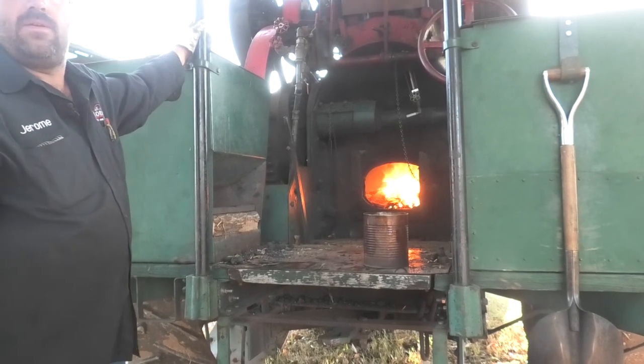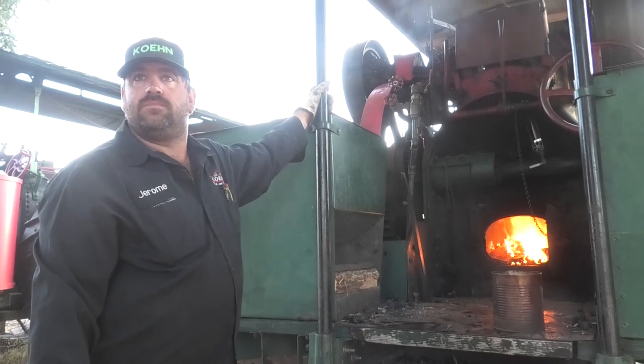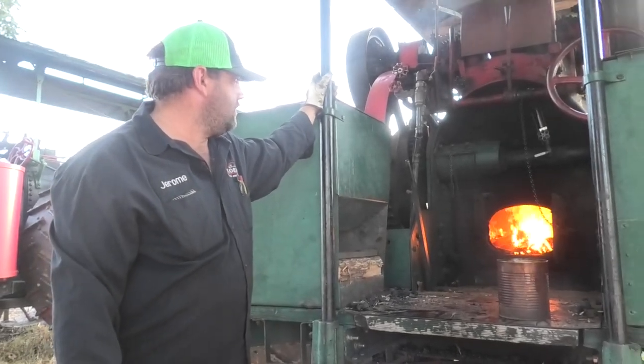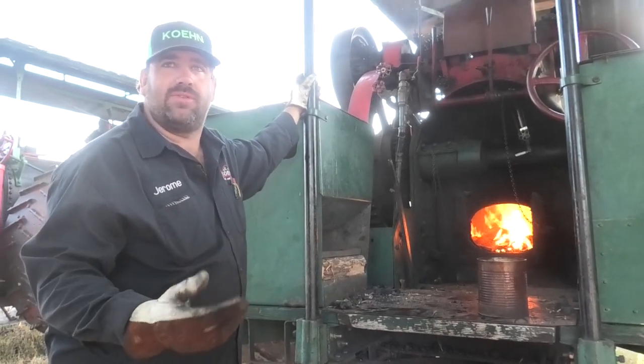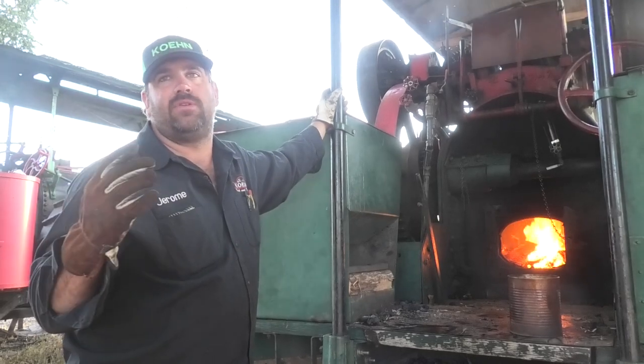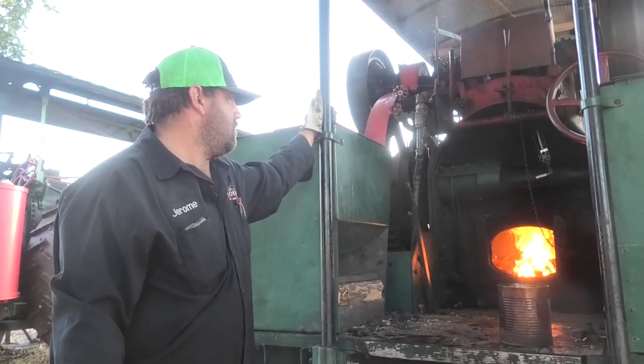I remember as a kid, there were still steam engines running through Pecos, Texas. I was always kind of fascinated by those hard black rocks that could burn. Yeah, and they burn hot. With the expansion and contraction with heat, we don't force feed these in the mornings. We try to ease them up to temperature. Right. You could get them hot a lot quicker. Yeah, but it's just a lot more stress on the boiler. That's understandable.